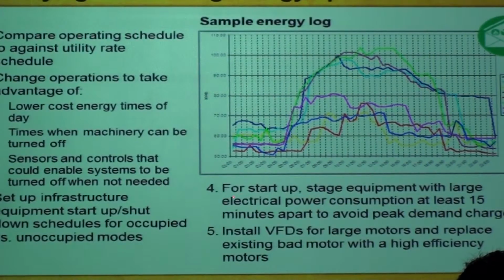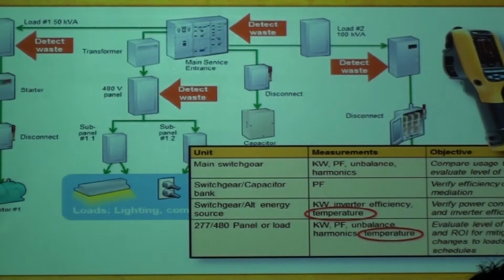Looking at startup stage equipments with large electrical power consumption, you gap it by 15 minutes, to avoid peak demand charges, so between repetitive instruments. Installing VFDs, a lot of people are doing that. From soft starters, they're going to VFDs for big motors. And you definitely want to replace all your existing bad motors with a high efficiency motor. Okay? So looking at these options, it's a good place to start. We know exactly where to look at energy options.